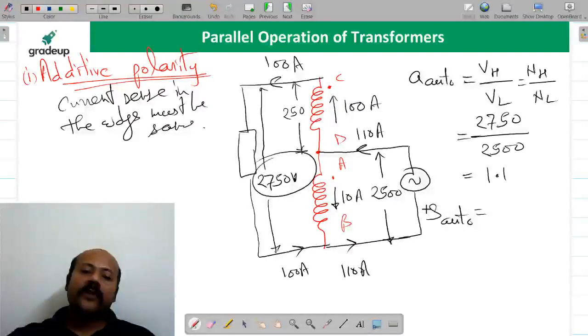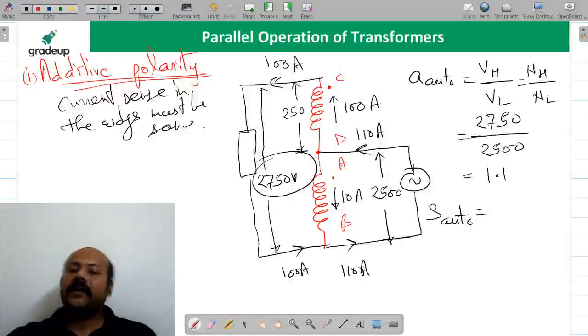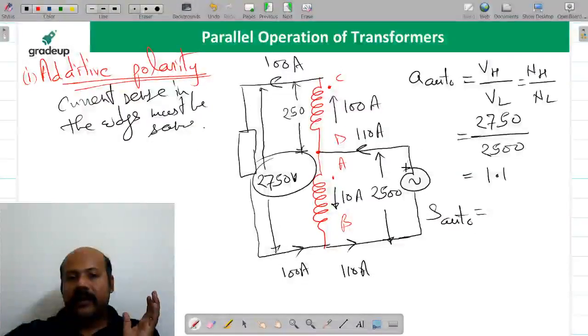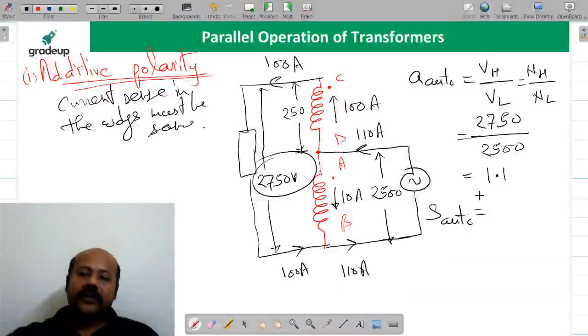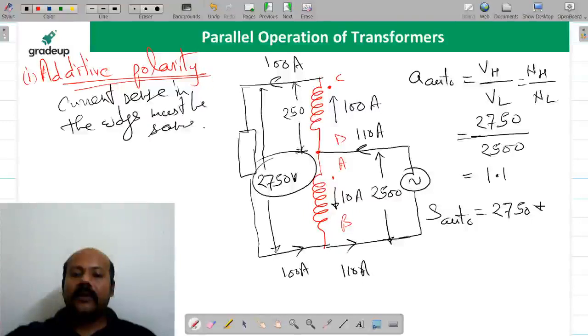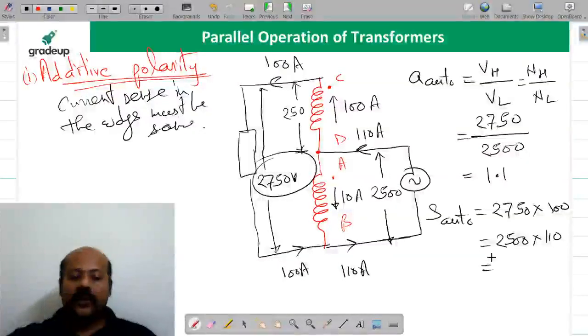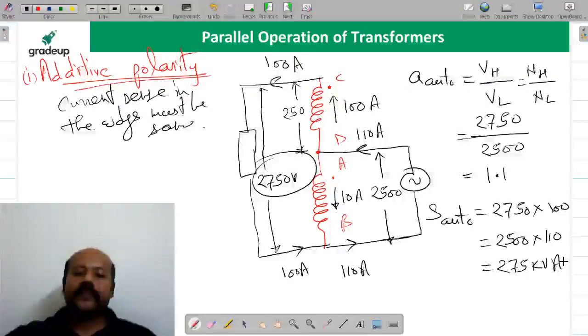Now let us see the kVA rating in terms of the auto transformer. You can find it from either side, load or supply, since power does not change. From the load side: voltage 2750, current 100. From the source side: 2500 multiplied by 110. Either way, you get 275 kVA.